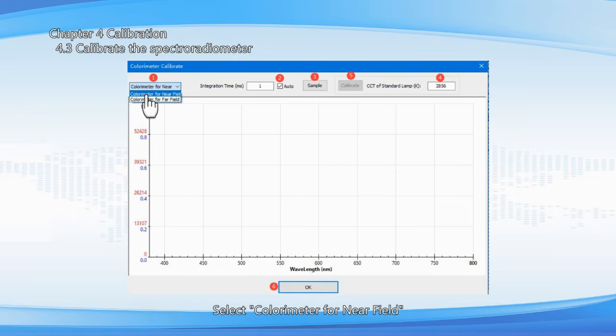Select colorimeter for near field. Always check auto for the integration time. Click sample. Then you can see the corresponding curve after the sampling is successful. Enter the correct color temperature value according to the standard lamp certification. Click calibrate. Then you will see the corresponding curve after successful calibration. Click OK to save and exit.